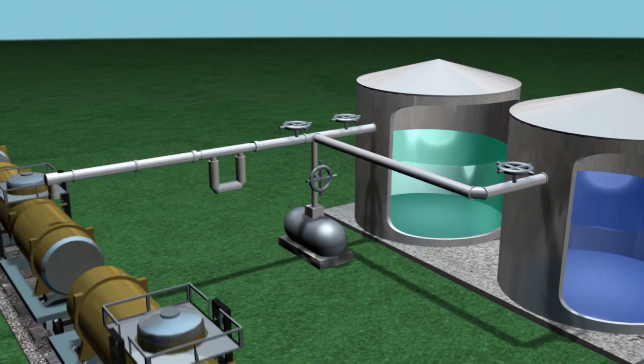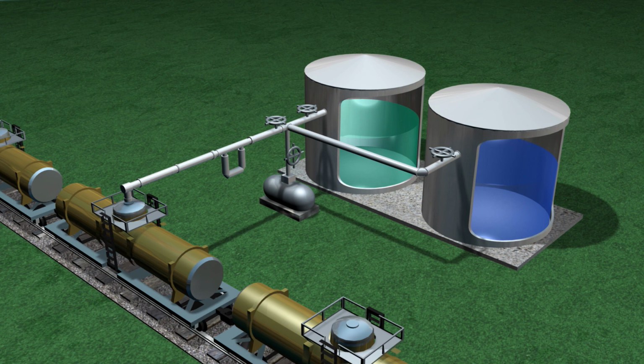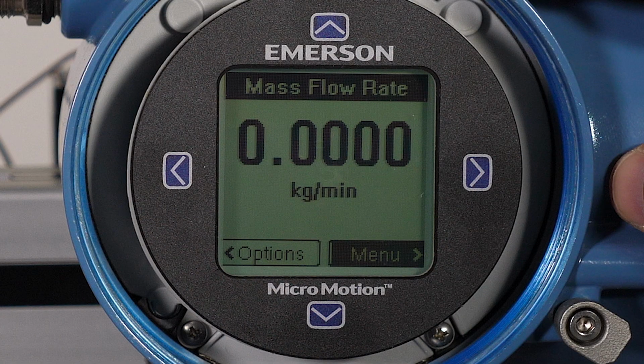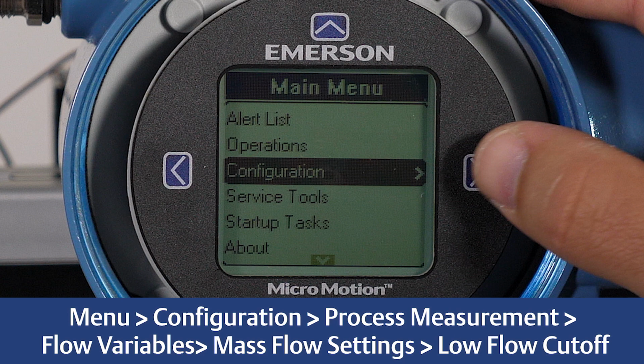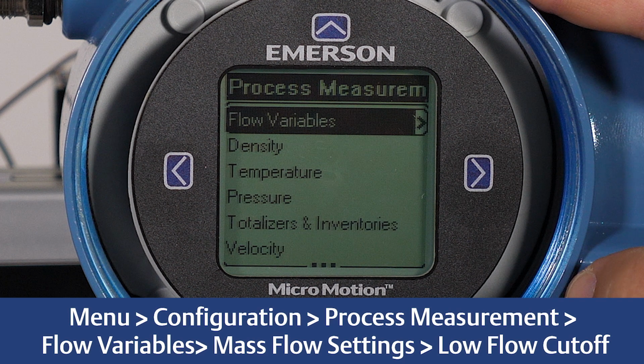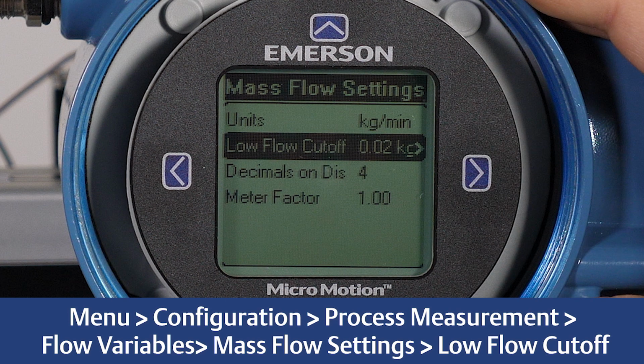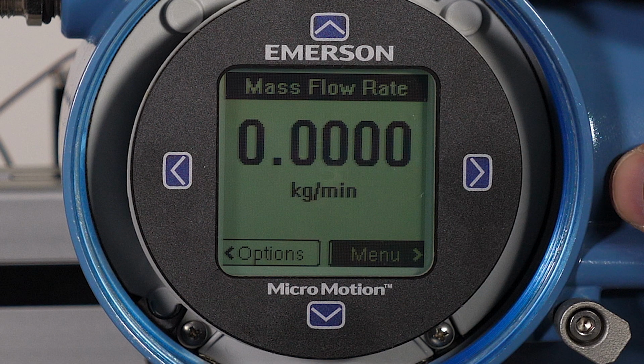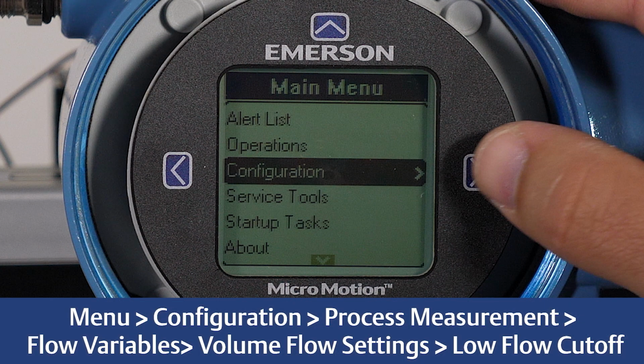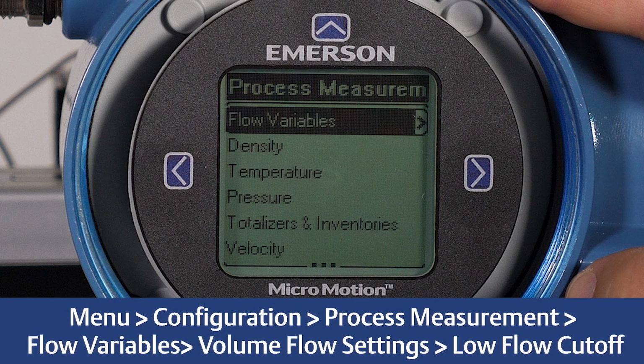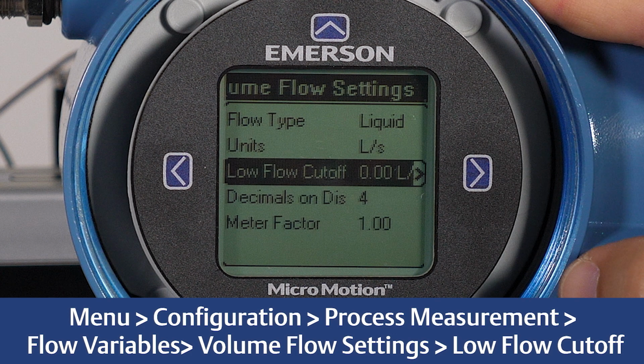Mass flow cutoff specifies the lowest mass flow rate that will be reported as measured. All mass flow rates below this cutoff will be reported as 0. The same definition can be used for volume flow cutoff. Refer to your specific transmitter configuration and use manual for proper cutoff value. For configuring mass flow cutoff, use the display and select Menu, Configuration, Process Measurement, Flow Variables, Mass Flow Settings, Low Flow Cutoff. For configuring volume flow low flow cutoff, select Menu, Configuration, Process Measurement, Flow Variables, Volume Flow Settings, Low Flow Cutoff.